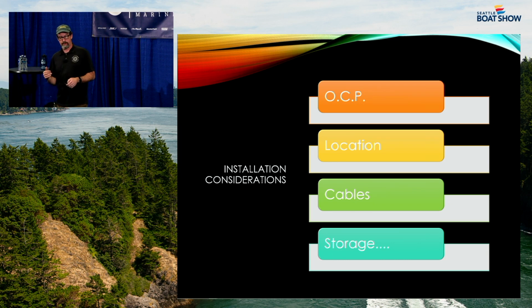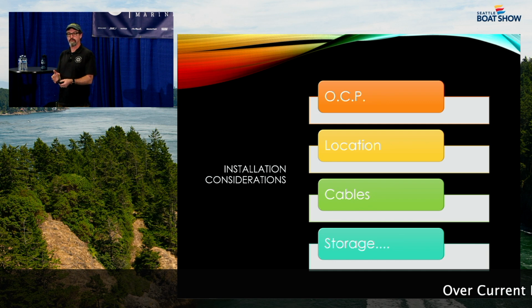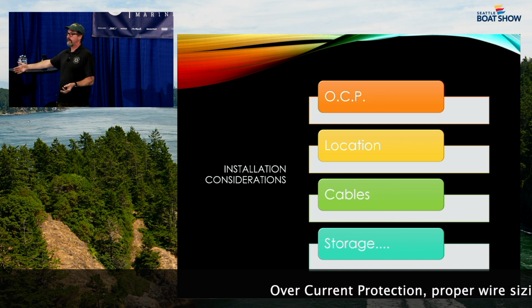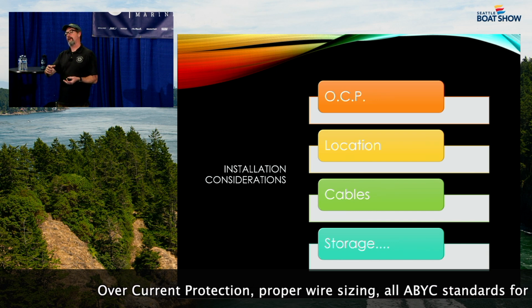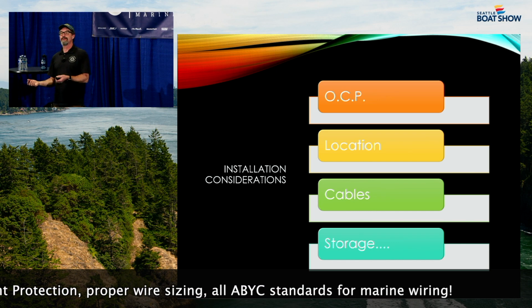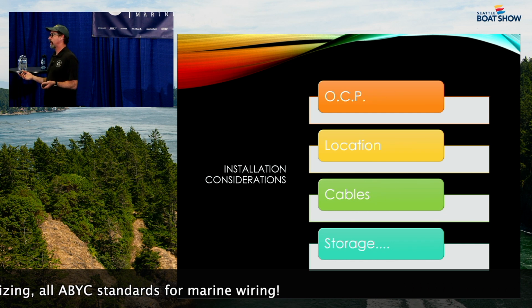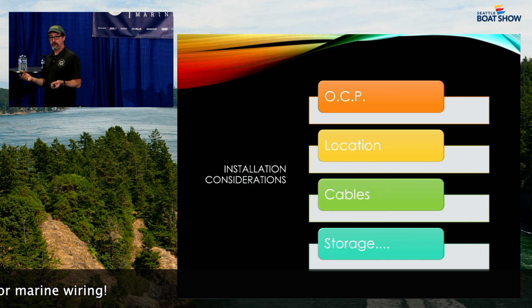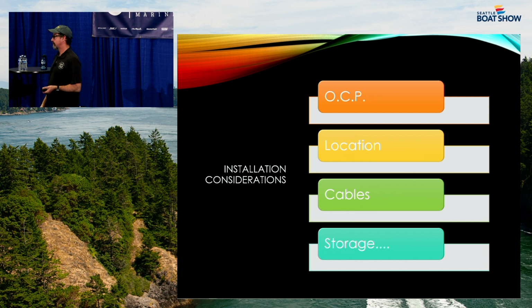We talked about lightning in a box. You've got to pay super close attention to overcurrent protection if you start dropping these in, especially if you're taking 2, 3, 4, or 5 batteries and making a big house bank. Put a fuse on every one of them, and that's so easy for me to say. Most of them require a Class T fuse. Has anybody bought a Class T 300 amp fuse lately? Yeah, a $75 fuse or something. So you're buying a $1,000 battery and you're like, oh, I didn't realize the fuse in the holder was going to be another $150. But you've got to stop that lightning in a box in the event of a fault, so make sure you're doing that.